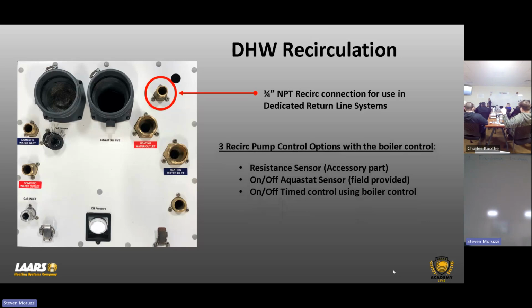You could buy the resistance sensor or surface mounted sensor for that pipe. You can use a mechanical on-off aquastat for DHW, or we have built-in time right on the program of the display, okay? An example of that is 20 minutes on, 40 minutes off. You can program that. So it's every hour it's running. You're not going to set this at 6 a.m. to 6:45. It's not done by that kind of clock. It's every hour you pick the time, how much time you want that recirc to run. Okay. So those are your three options.